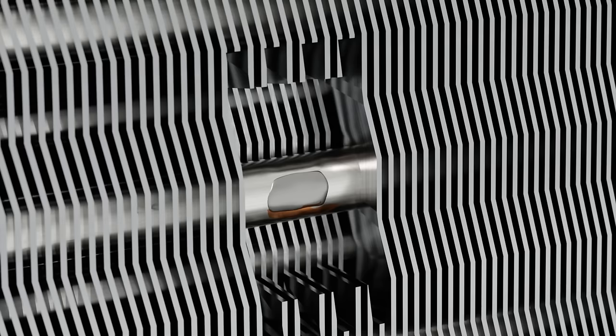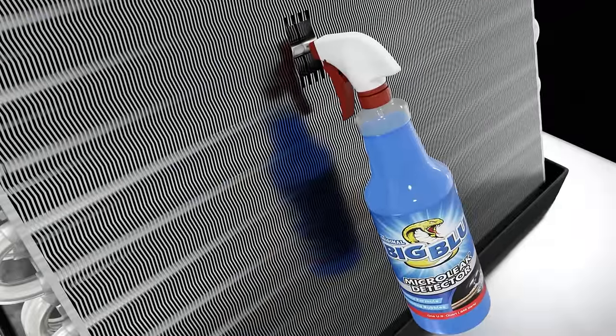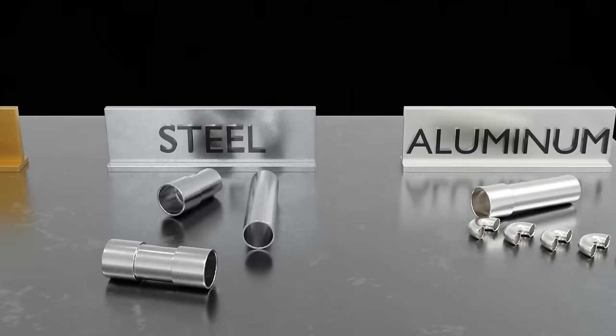Always follow the specific manufacturer instructions. There are other aluminum repair rods that have a flux directly inside the rod, which can also be used effectively. When complete, clean off the area. Pressure test and bubble test to confirm that you've completed a leak-free repair. Aluminum can be successfully repaired in many applications. We've done so in everything from tubing, coil pack, and even micro-channel when using proper products and techniques.